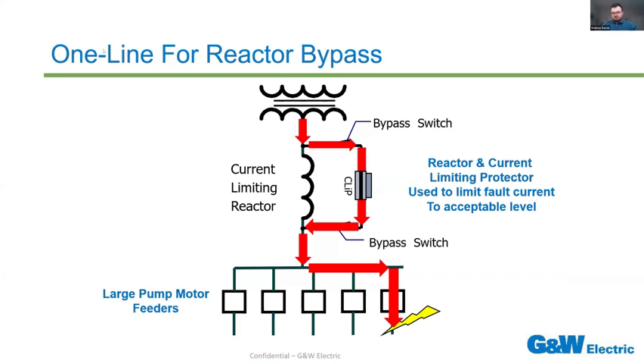So here's an example of one line of how it looked. And the source under normal previous operation would just go through the reactor to the downstream pump motor feeders. That would obviously incur the power quality issue if that were to occur. So what they did was they bypassed that using the clip.